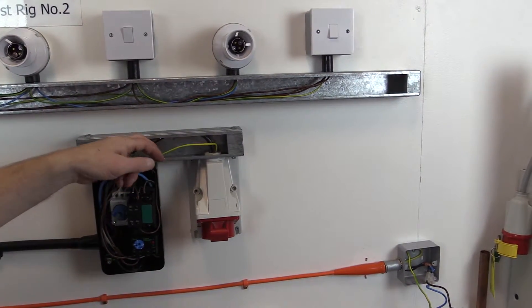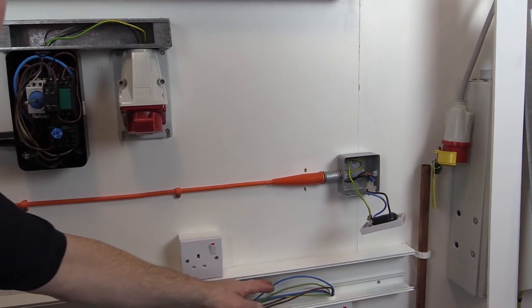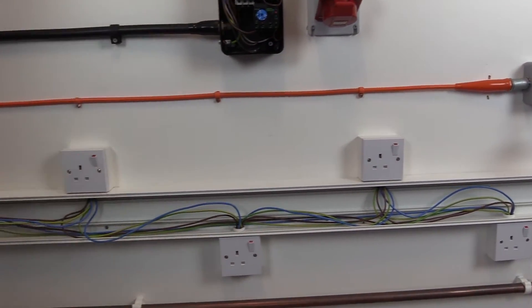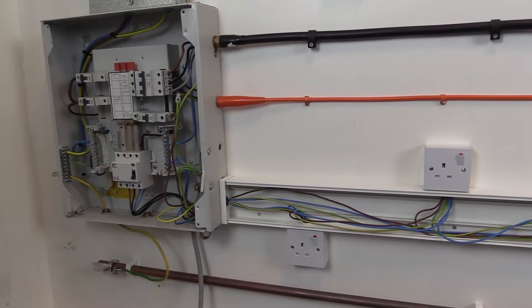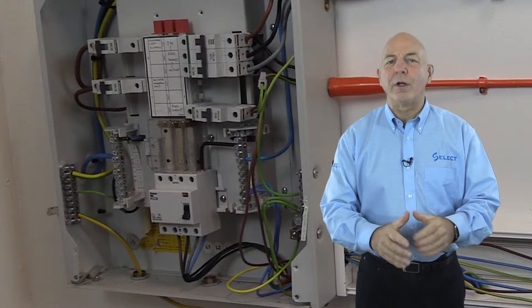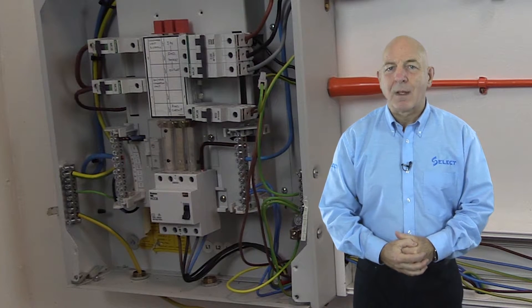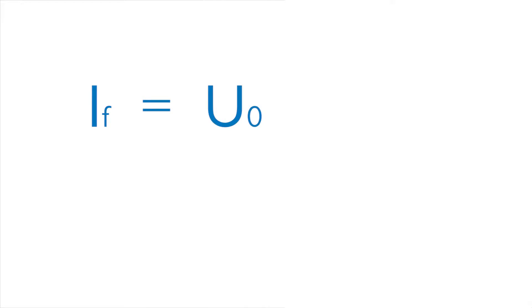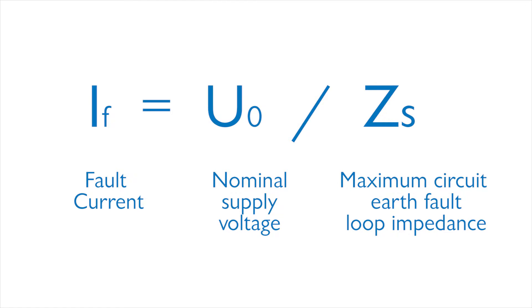These provide a means of connection to earth for the exposed conductive parts of installed equipment and form part of the low impedance path, which is known as the earth fault loop impedance. The amount of current flowing in the circuit during an earth fault condition is dependent on the earth fault loop impedance and can be determined using the formula IF = U0 / ZS, where IF is the fault current, U0 is the nominal supply voltage, and ZS is the maximum circuit earth fault loop impedance.